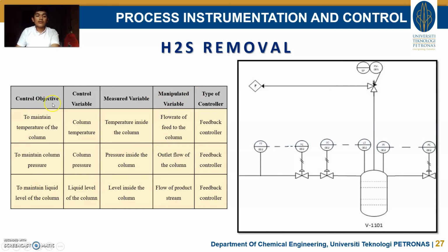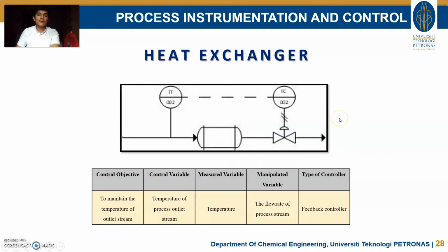And the last one is to maintain liquid level of the column. The control variable is liquid level of the column. The measure variable is level inside the column. And the manipulated variable is flow of product stream. So for H2S removal, we install three types of controller, which is flow controller, level controller, and also pressure controller.